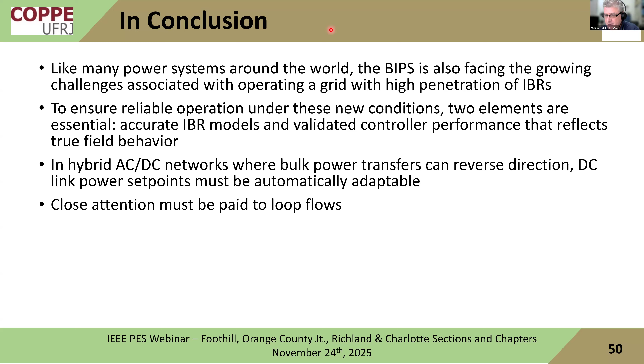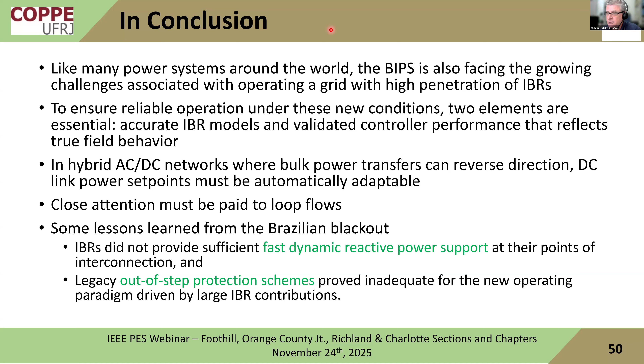Some lessons learned from the Brazilian blackout. IBRs did not provide sufficient fast dynamic reactive power support at their points of interconnection, and the legacy out-of-step protection schemes proved inadequate for the new operating paradigm driven by large IBR contributions. So this closes my presentation. I thank you all for listening, and I am now open for the Q&A.